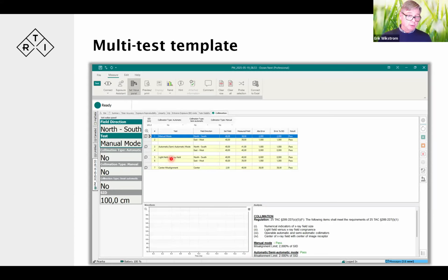And here's another one where we have a manual entry, where we key in the difference here, the measured field. We measure it and punch it in by hand, because we don't have any instruments that do this for us at the moment. So we have to key in the size of the values here based on a phantom or similar. But the calculations can be done in the template to give us a pass-fail based on parameters that are set. For instance, 2% of the SID for a deviation for light field and X-ray field. So these calculations are similar to what we have in Excel.